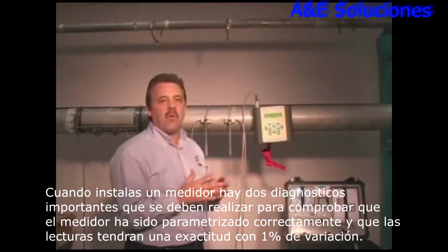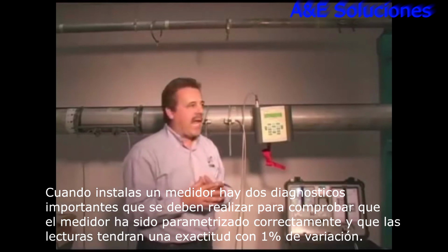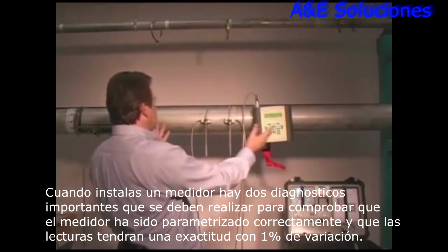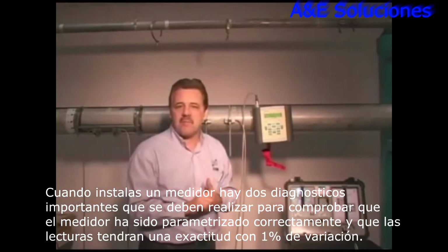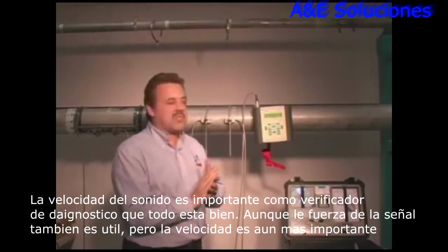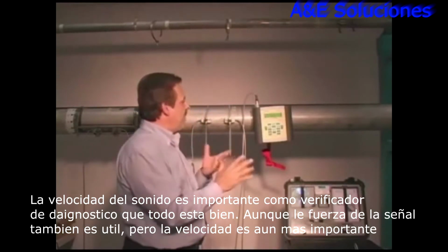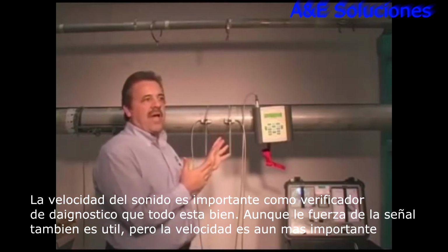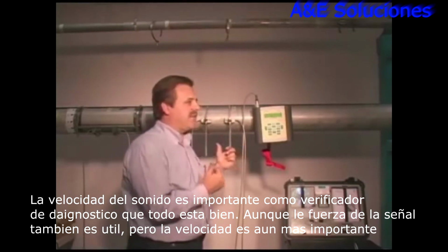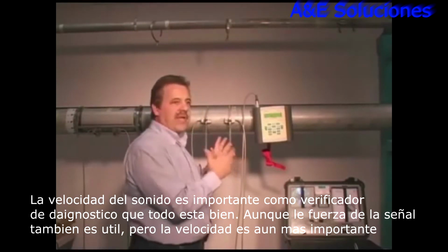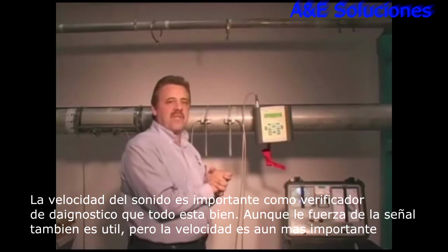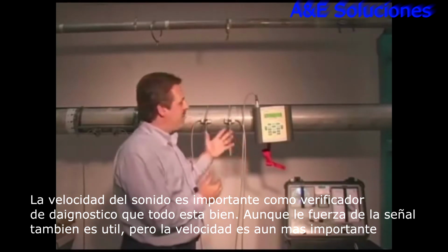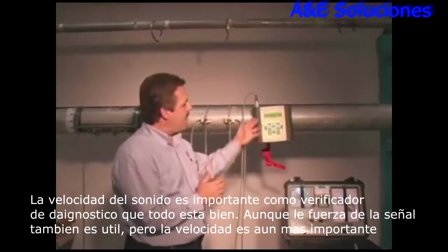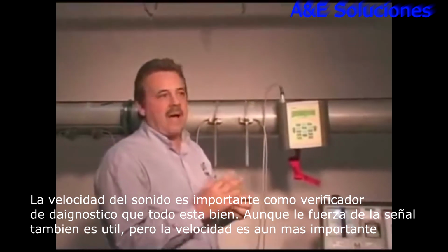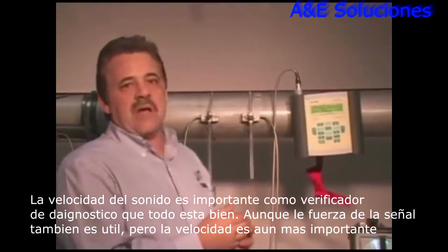The meters are all wet flow calibrated to 1%. And given your piping conditions, if you have a fair straight amount of pipe, you're going to be in that 1% range. So sound speed is important as a good diagnostic check, and signal strength as well, but sound speed really tells you that you've done everything right. If, for example, I would have programmed the pipe dimension wrong, I would have seen an error in the sound speed. Now, we're talking about the sound speed of water here.